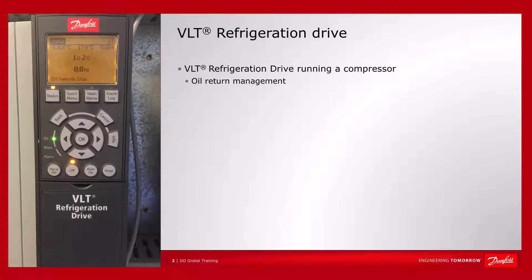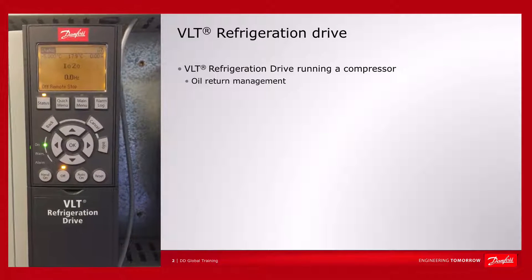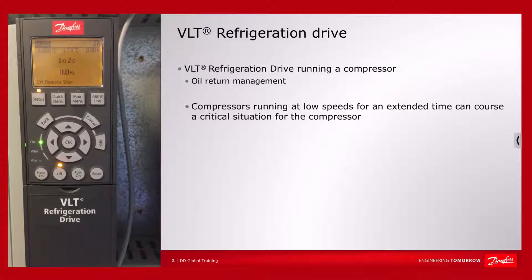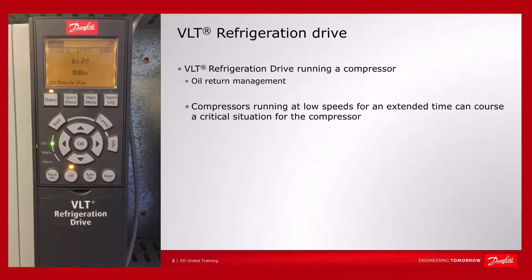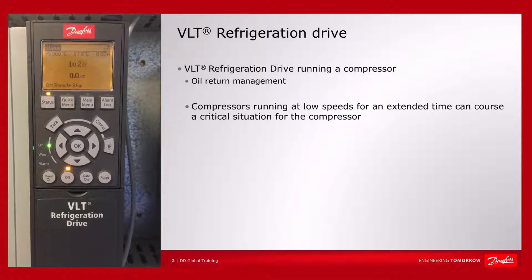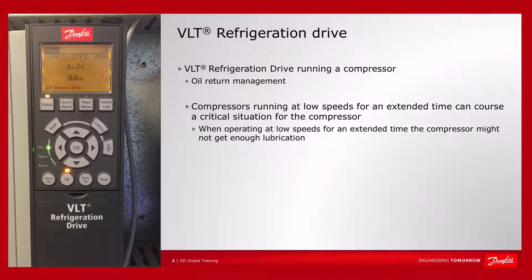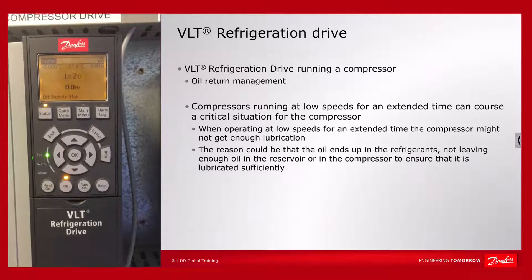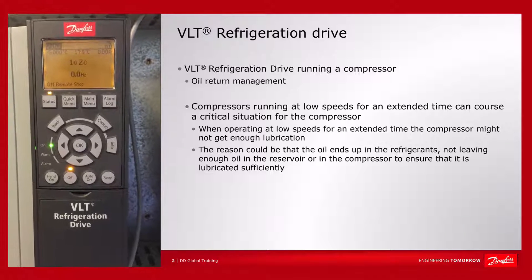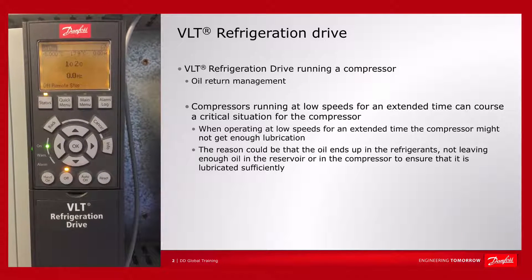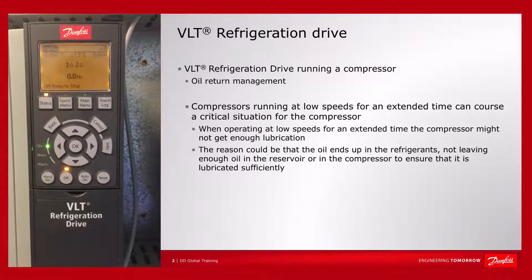This is a Danfoss refrigeration drive. I will tell you how we can program the feature oil return management. When a compressor is running at low speeds for some time, it can be a dangerous situation because it might not get sufficient lubrication. The reason could be that oil ends up in the refrigerant and there is not enough oil in the reservoir or in the compressor to ensure it is lubricated sufficiently.